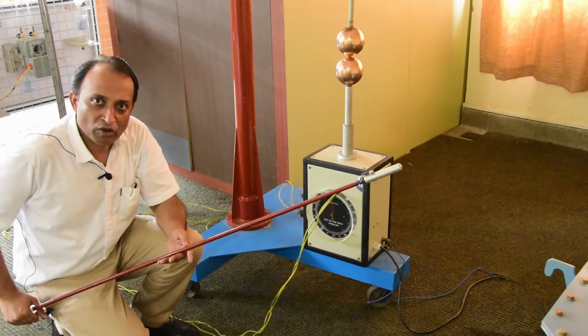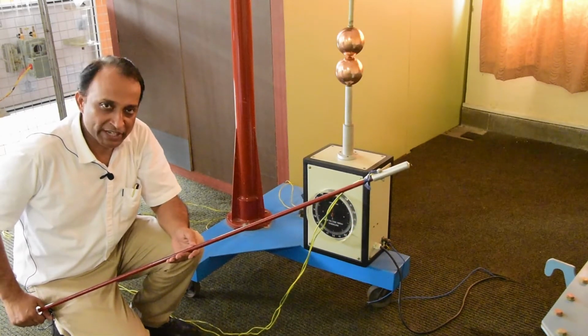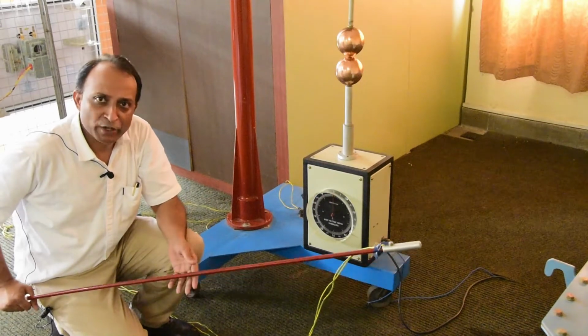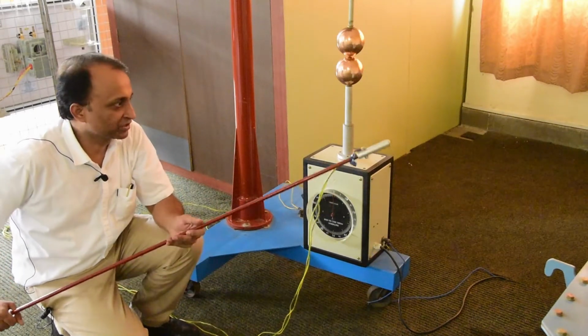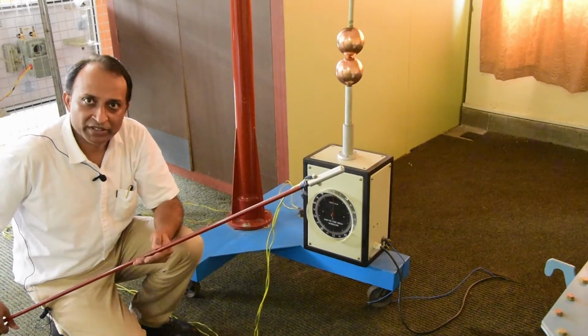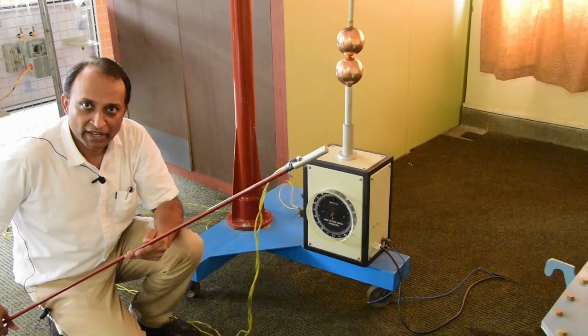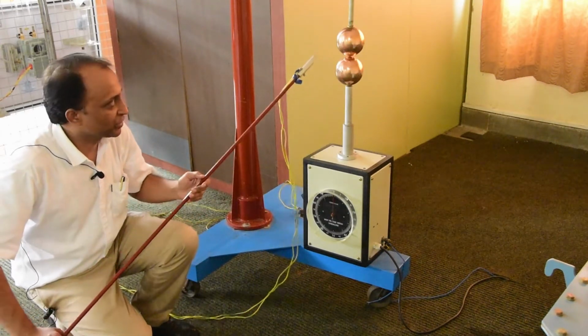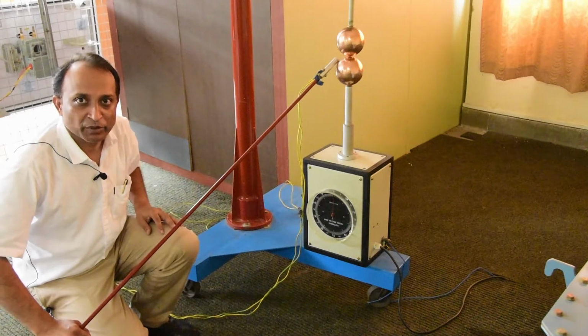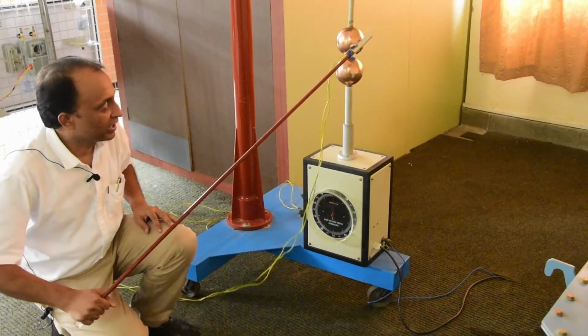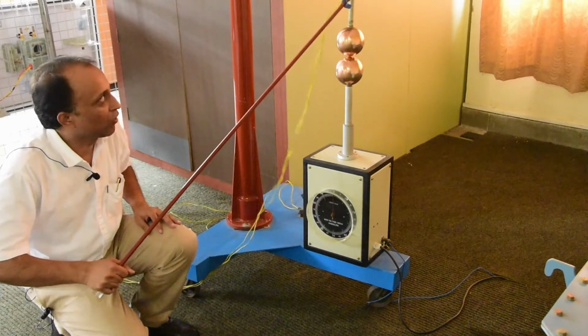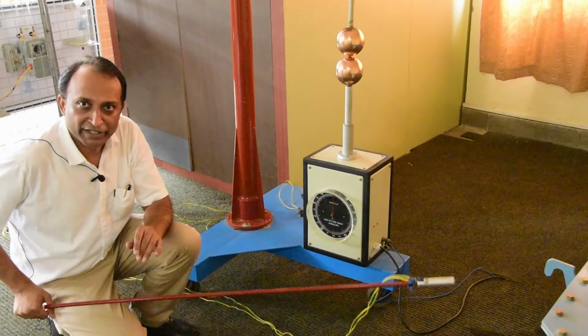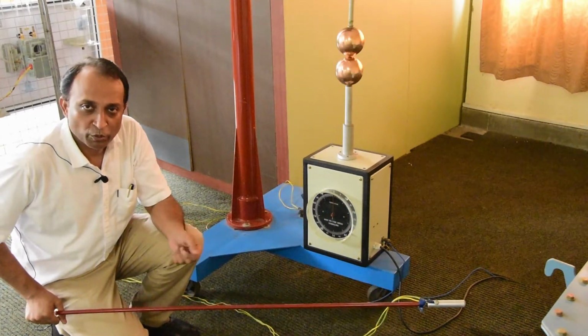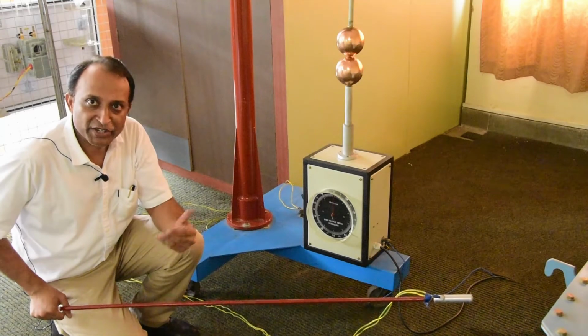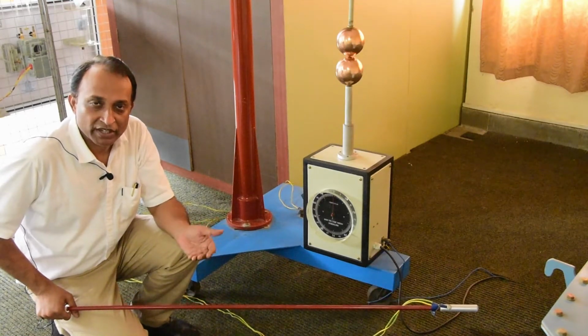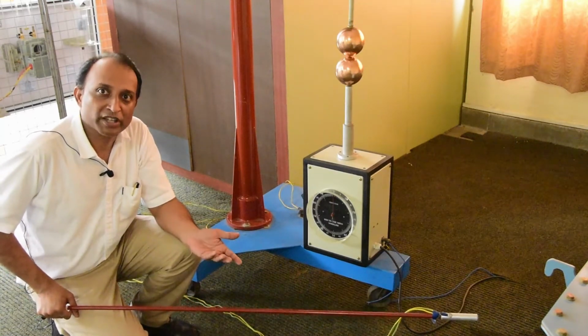Whenever we work on the high voltage laboratory experiments, before entering the cage, there is a practice to de-energize the circuit, to disconnect the supply, and to ground all the metallic objects. Like here I am touching this one. So this will be grounded, this will be grounded. All metal parts are connected to the ground in order to discharge any static charges present on them due to the previous or earlier performance.